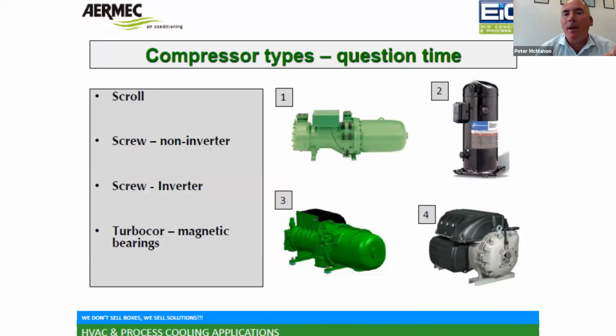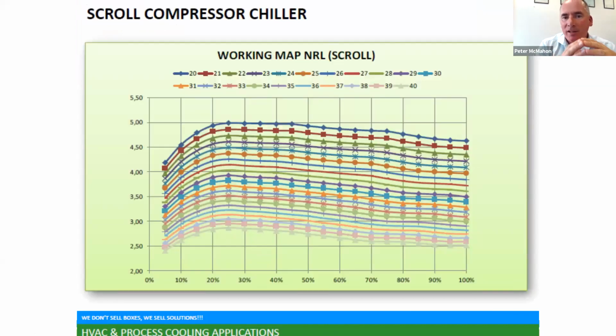The other thing I want to mention is different compressors have different part load efficiencies. Now, as I said, I'm going to brush over this very, very quickly, but the only thing I want to try and get across to you guys is chillers are at their least efficient when they run to 100% load. So these couple of graphs here are going to show you up at 100% load here, you can see over on the right-hand side, these are all just different ambient curves, by the way. So if we pick the curve in the middle here, let's say the green one, you can see that's an ambient of 27, 28. That's what we typically use in Ireland. The efficiency increases as the load drops off. Okay, so that's a scroll curve.